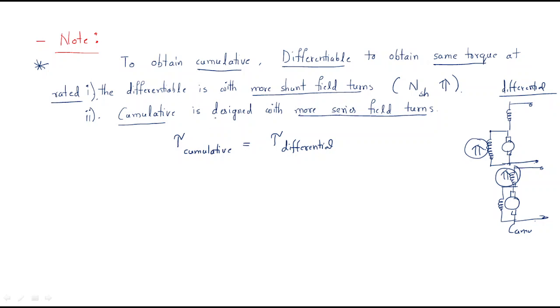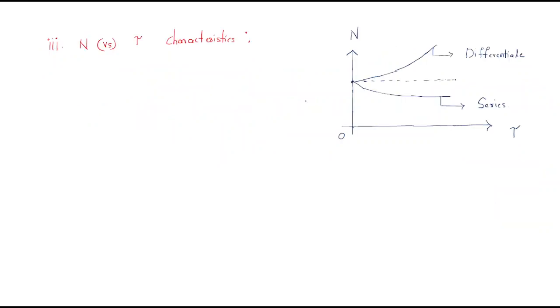This is a very important condition. For a compound motor, the differential compound motor torque and cumulative compound motor torque at a particular rated current will be different. But to maintain the same torque: the cumulative compound motor should have more series field turns, and the differential compound motor should have more shunt field turns.